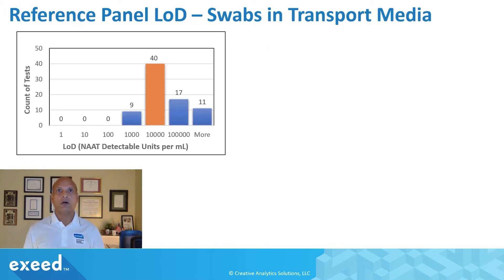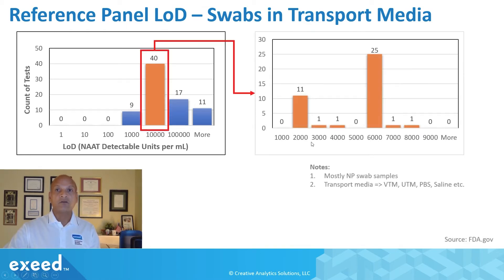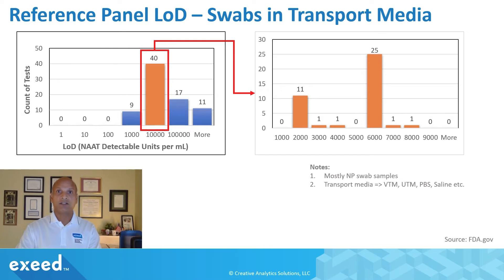Here is a summary of swabs in transport media — most of them are NP swabs. As you can see, the majority of tests are showing an LOD of about 10,000 NDU per mL. The largest bin ranges from 1,000 to 10,000, with 40 tests in that bucket, and the majority of those have an LOD of about 6,000. NAAT stands for Nucleic Acid Amplification Test — this is the standard metric FDA is using to report LOD data.